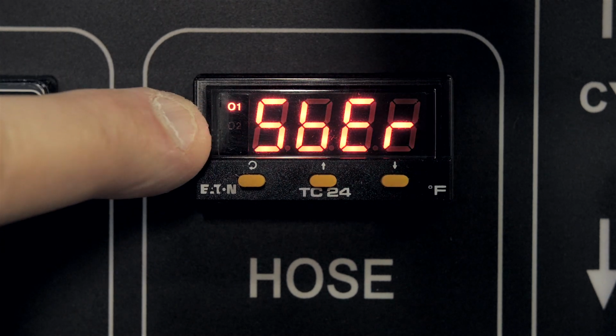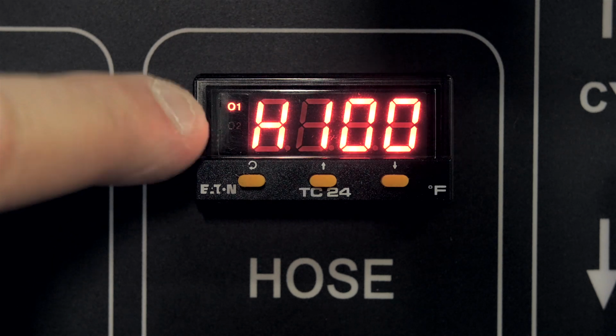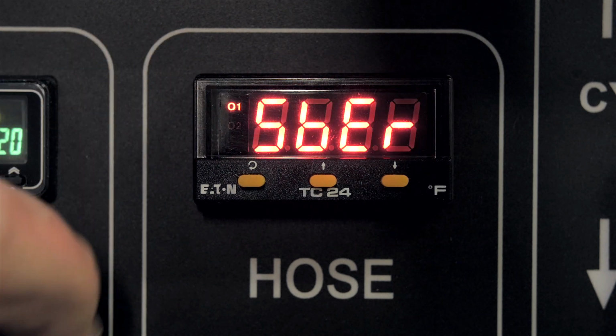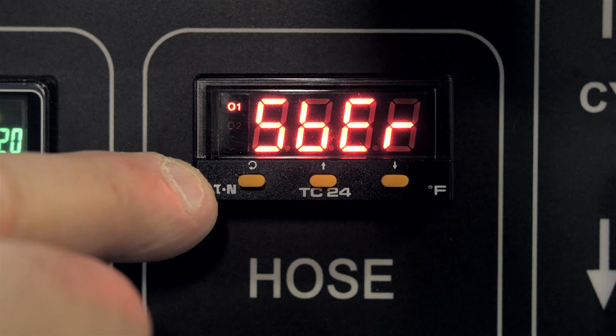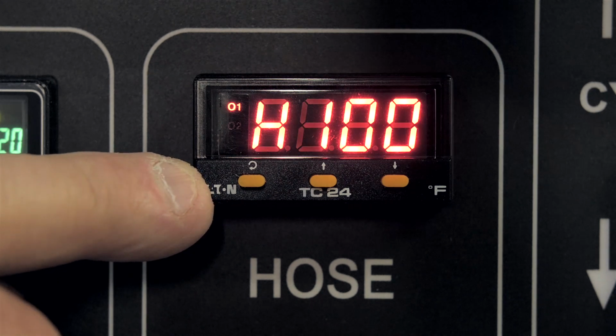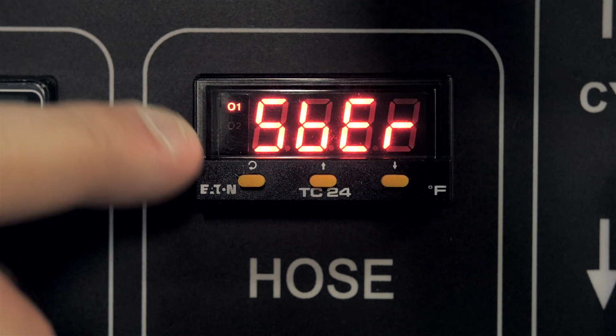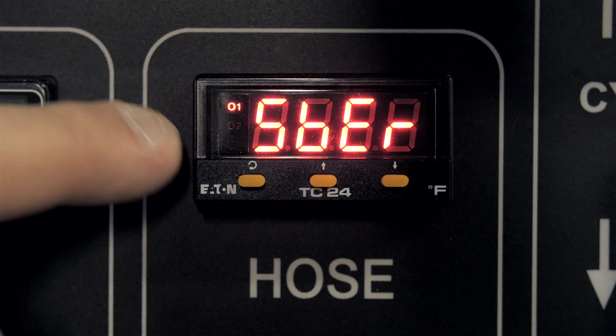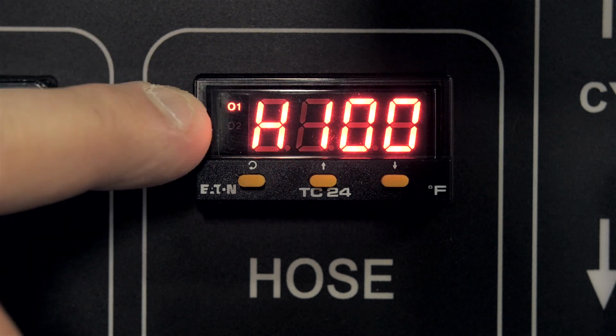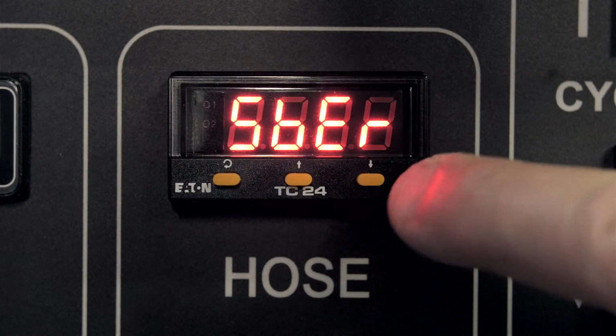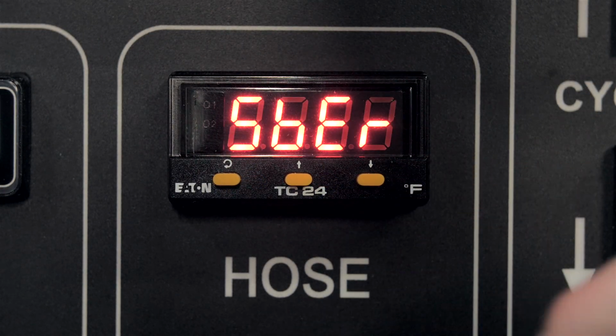What we're doing here with this manual override is a temporary fix, so we can continue to work until we get a replacement part, either a new sensor or we fix the break within the hose. As we're showing this error code, you'll notice that the amp light down on your hose transformer is off.